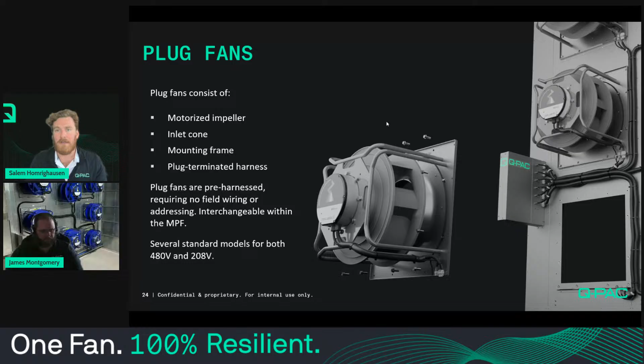So the control panel, as I said before, is a product that we basically had to start building because we wanted a little more control over the controls for the building and how you would actually operate the Q-PAC fan. As it was a requirement previously, now it is optional, since the Q-PAC fan can be operated just with that power and control signal. But currently the control panel is a great option for people, especially if you have a building that's maybe not as sophisticated. Maybe it doesn't have a very sophisticated BMS system that's really controlling your airflow or reporting many values.